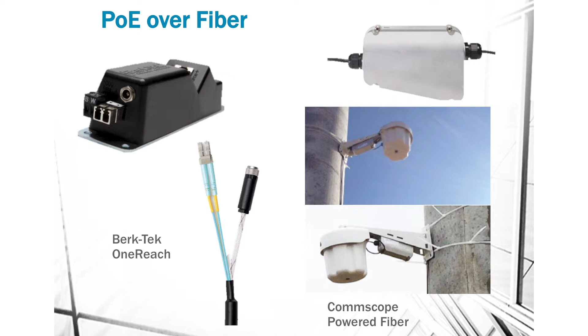Going back to your discussion about surge protection and lightning protection, even with these composite cables, that's a consideration we have to build in. We have to split the cable apart and route the copper section through surge protection if we're going out to a light pole in the middle of a parking lot. That's another complicating factor.